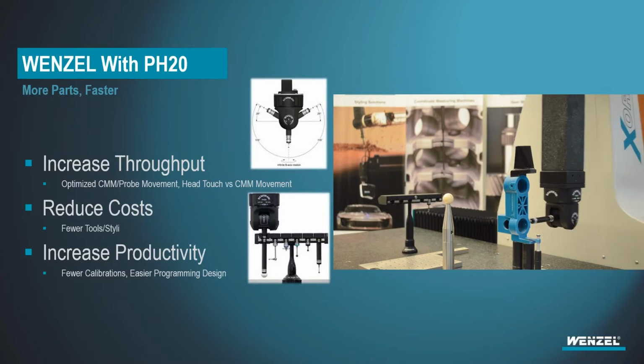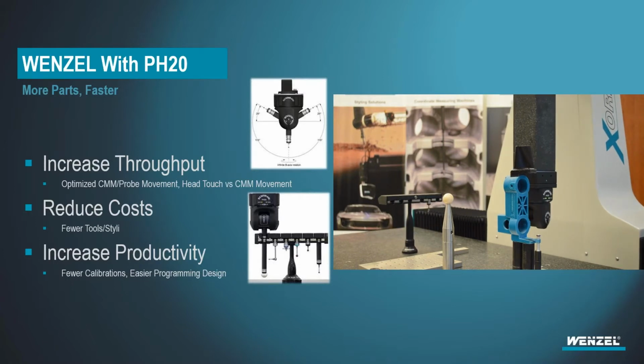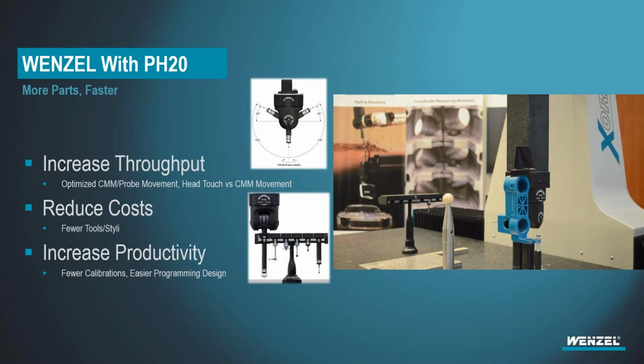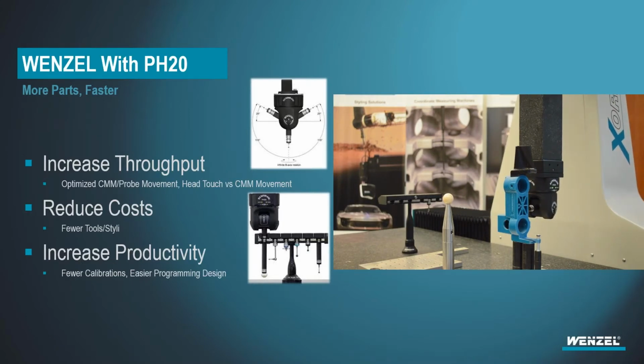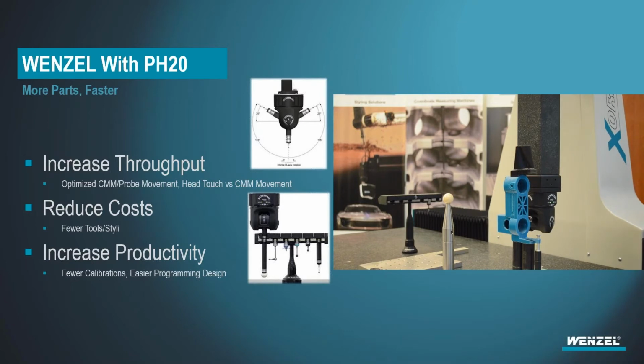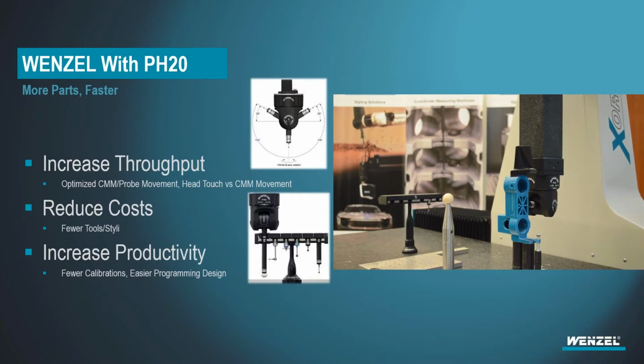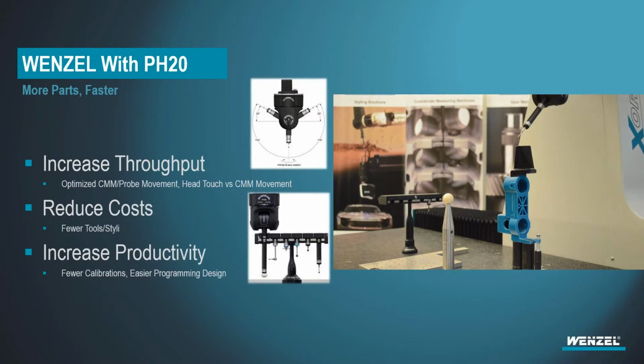If we keep the CMM steady in place, the very, very lightweight probe can take the individual points that it needs, the head touches. Very, very quickly, you can collect, say, 30 points in a circle in the time that it might take you to take your standard 4 or 5 points in that same circle. Ben's going to dig into the programming of that, so I'm going to stay off that topic a little bit. We'll stay here just with this video.